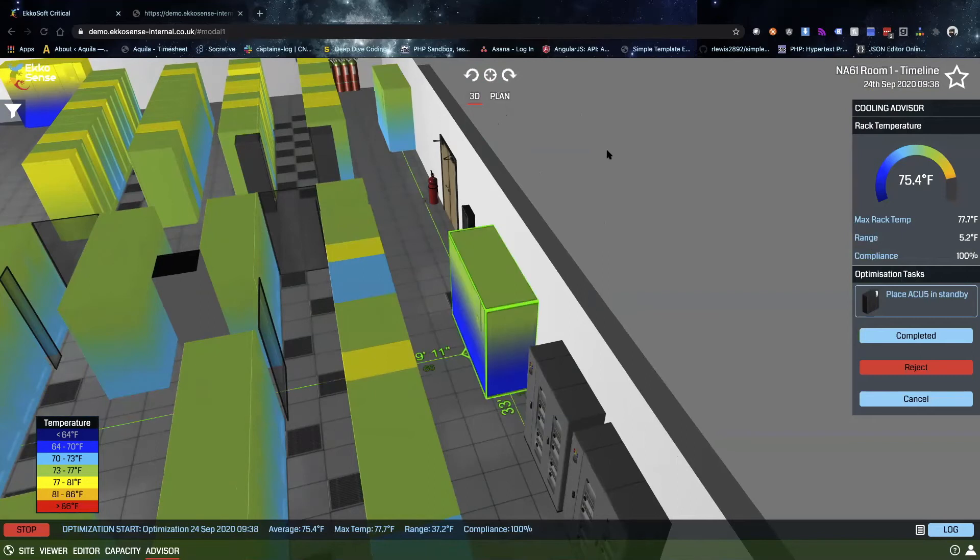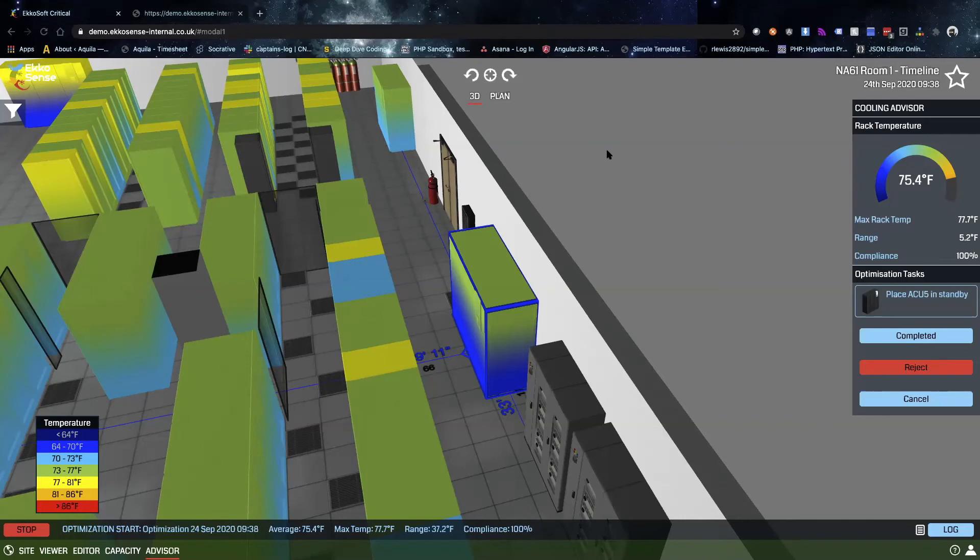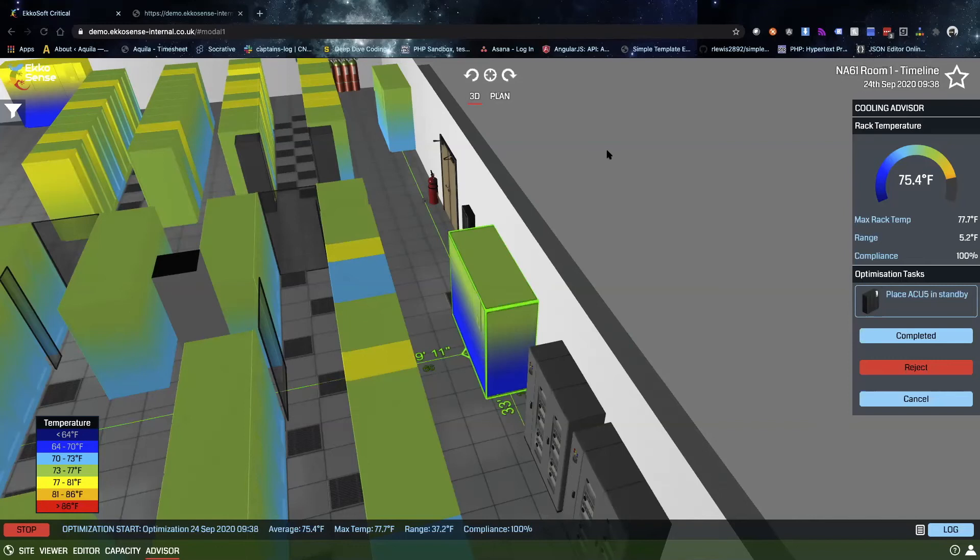Turning it off will likely improve the conditions in the room while saving operating cost. This recommendation is to turn this cooling unit off and place it in standby. As Dean mentioned, the software doesn't control anything and that was a very intentional decision. This puts the power in the hands of the site people and also provides a nice educational tool. It's like having a cooling optimization consultant on staff 24/7 to provide recommendations and guide the process as things change in the room.